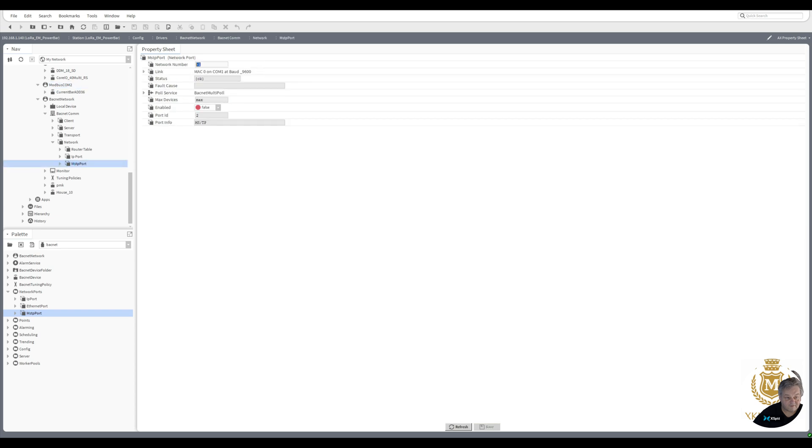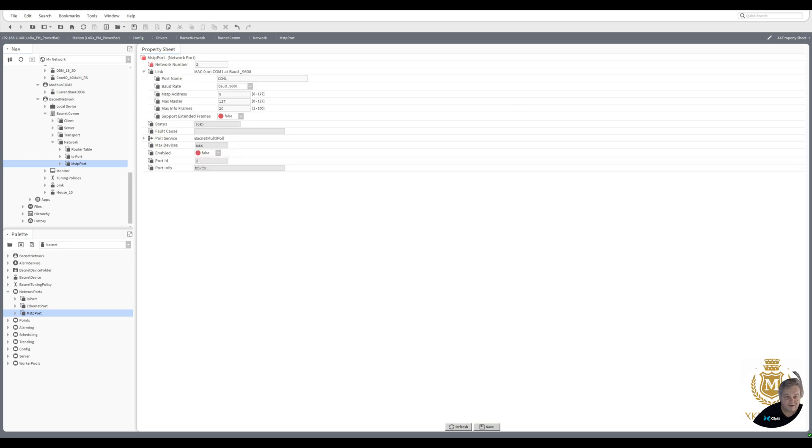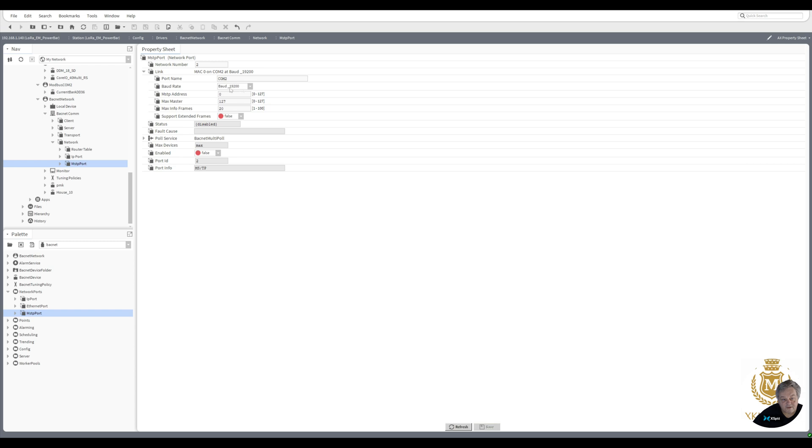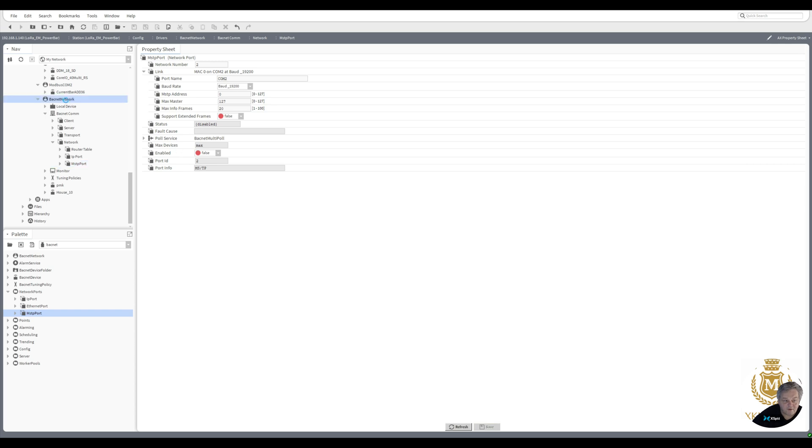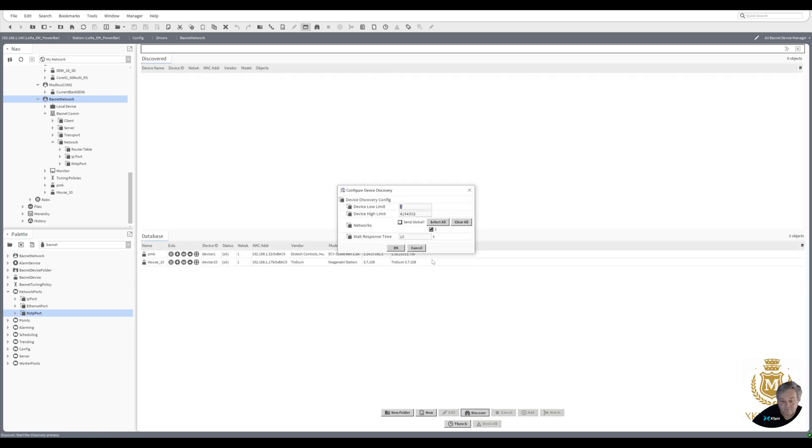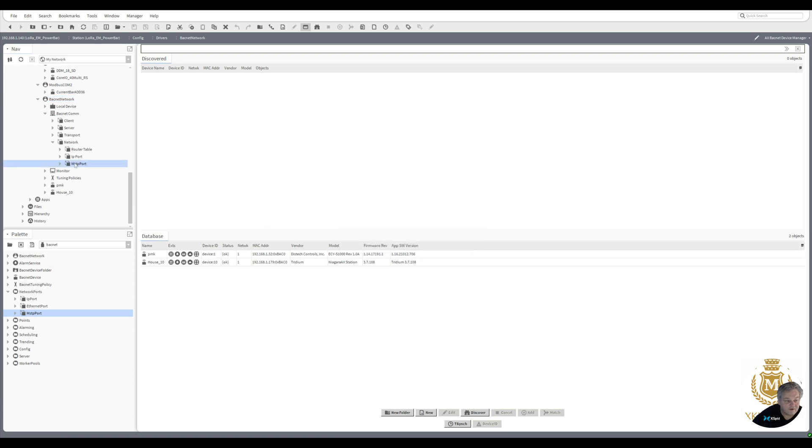Now go back to MSTP. We need to set this up. We need to give it a network number, so I'm just going to give it network number two because we've already got one for the IP. This is going to be COM2 and then you can set the rate to whatever you want, so I'll just do 19.2. Save. Now the 19.2 baud rate must be the same rate when you're talking MSTP as the other devices that you are connecting to. So if the fan coils via MSTP, the baud rate must be 19.2 on all the fan coils. You basically find out what all the fan coil baud rate is talking at as a BACnet controller and set your MSTP port up to be the same baud rate.